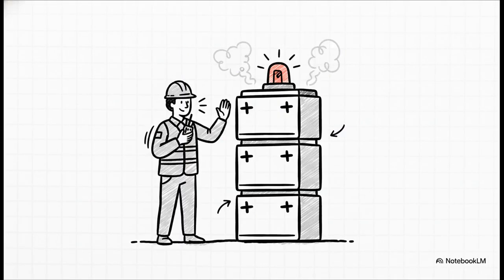If you even suspect a power issue, or say you smell smoke, your only job is to observe, read the LED status, and report it. Never, ever try to be a hero with a live battery bank. Unless you have specific power training certification and the right electrical PPE, you are strictly there to monitor. You read the alarm code, whether it's mains fail or rectifier fail, report it directly to the NOC and you step back. Batteries act as massive energy reservoirs. Even if the system looks completely off, they are fully charged and ready to discharge all that energy the second you touch the wrong point.